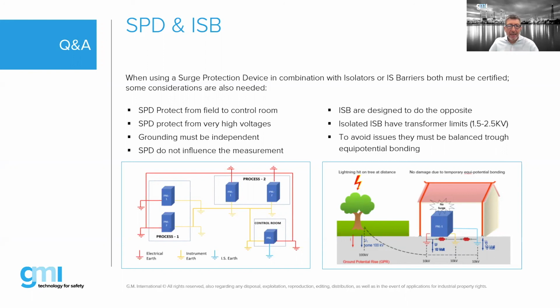Basically, SPDs, or TVS as our guest calls them, are designed to protect from the field to the control room. So if an accident happens, some lightning going into the field wiring, the high energy comes back into the control room. Now, an IS barrier, at the very opposite, is protecting the other way around. From the control room to the field. It is, to an extent, although you could say that an SPD, in effect, is also protecting against those large surges that could come into your control panel, and that, if left unchecked, would come down that cascading system and eventually wind up at the ISB.